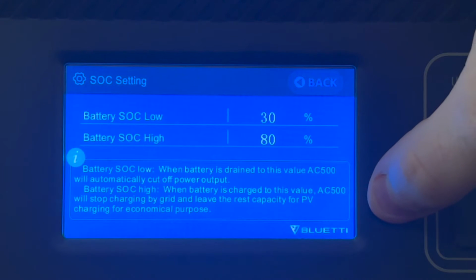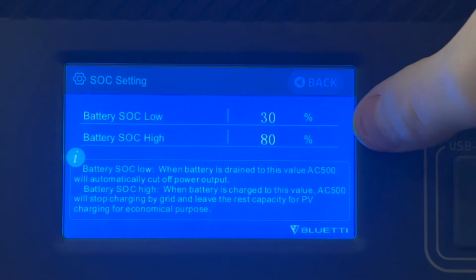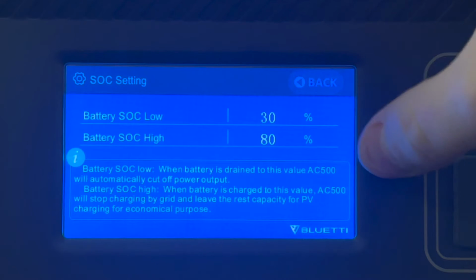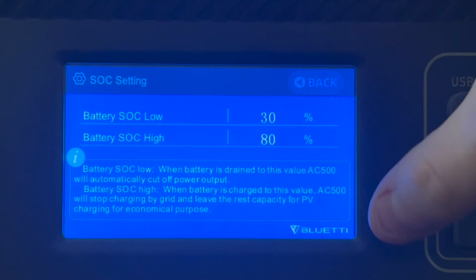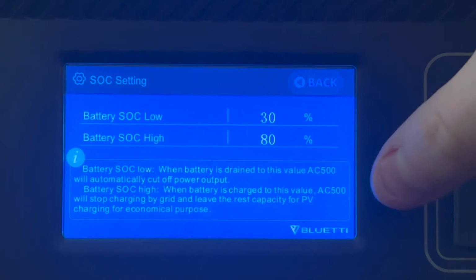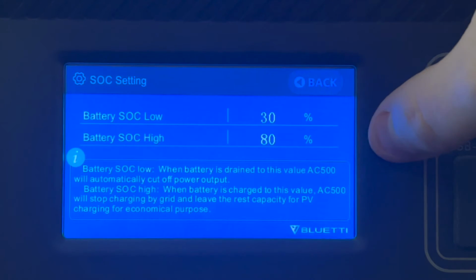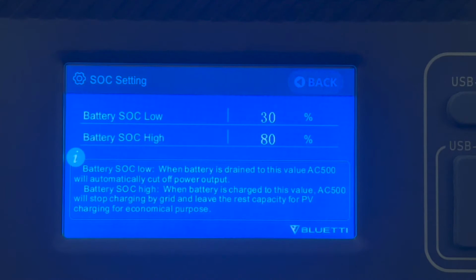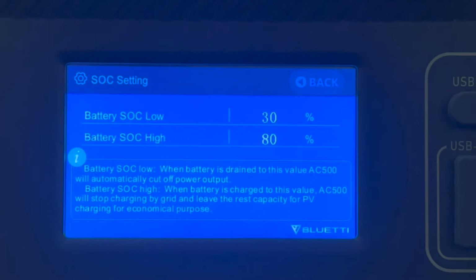So high, it will stop charging off the grid and continue charging off PV above this number. So if you only want it to charge to 80% on PV, even with solar plugged in, and you don't want it to charge higher than 80%, this setting isn't going to do that for you. This setting will get you grid to 80%, and then when it's done getting to 80% on grid, it will continue up to 100% on PV. If you want to prevent it from charging to 100% by any means, you will have to put a switch in to disconnect your solar panels to prevent it from getting to 100%.